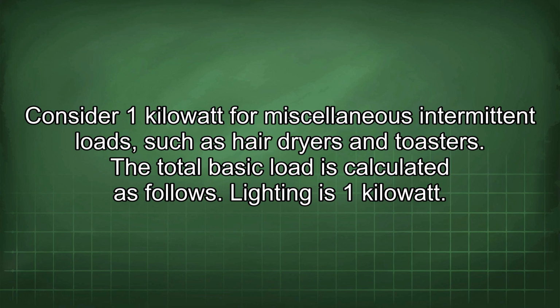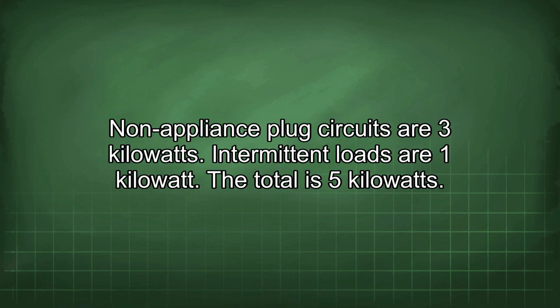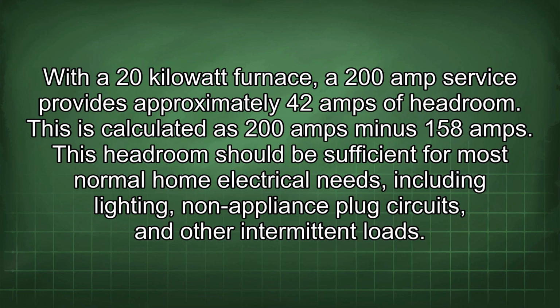The total basic load is calculated as follows. Lighting is 1 kilowatt. Non-appliance plug circuits are 3 kilowatts. Intermittent loads are 1 kilowatt. The total is 5 kilowatts. With a 20 kilowatt furnace, a 200 amp service provides approximately 42 amps of headroom. This is calculated as 200 amps minus 158 amps. This headroom should be sufficient for most normal home electrical needs, including lighting, non-appliance plug circuits, and other intermittent loads.